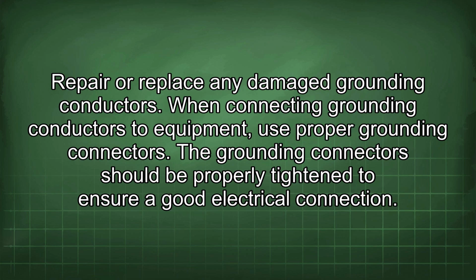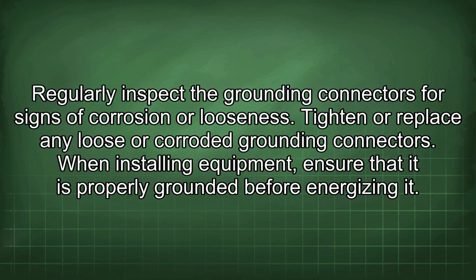When connecting grounding conductors to equipment, use proper grounding connectors. The grounding connectors should be properly tightened to ensure a good electrical connection. Regularly inspect the grounding connectors for signs of corrosion or looseness. Tighten or replace any loose or corroded grounding connectors.